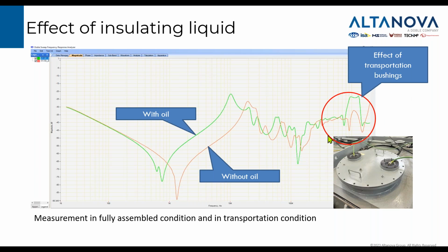Here in this example, we also had the effect of high voltage bushings, which were missing during the second test without oil. Instead of that, we had small bushings as seen here in this picture. The history is that this was a brand new transformer, which was first tested with oil during FAT tests, and then without oil in transportation condition. So that means the oil was drained, and these bushings were replaced with small bushings connected to the windings just for the purpose of this test. This is more and more often done in the industry. This technique is used to assess transportation. For transformers with 400 kV bushings, we cannot transport it with the bushings. They need to be disassembled.